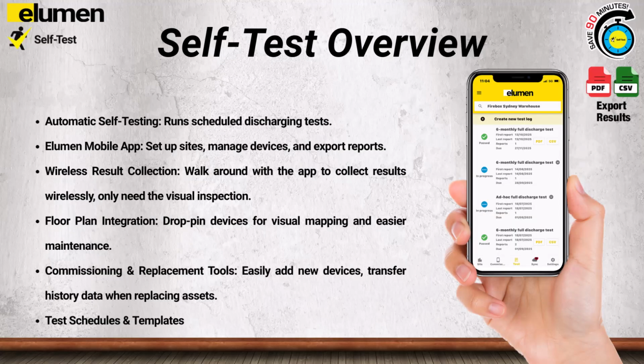So what is self-testing? It's a smarter, automated way to test emergency lighting devices. Key features include automatic scheduled discharge testing, every 60 days by default, with the option to adjust frequency and timing.